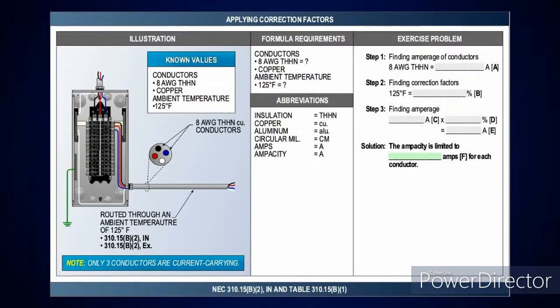One important thing to keep in mind: if you're only routed through that high ambient temperature for less than 10% of the run, you don't need to derate it. Go look at NEC 310.15 B2 exception. We put those in our publication for things for you to consider. These are things that could be on the test — and our code loops help you navigate all the different steps to verify you're on the right track.